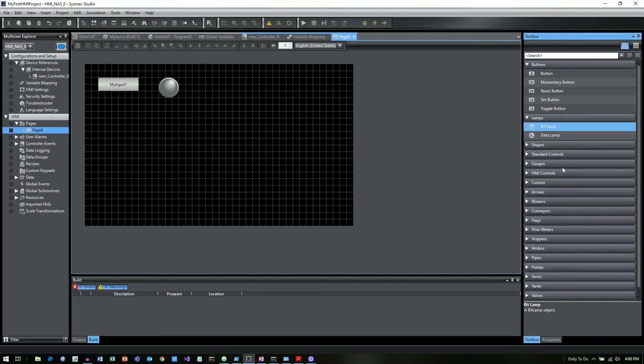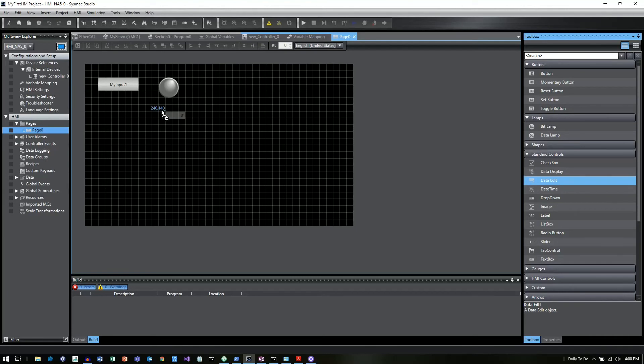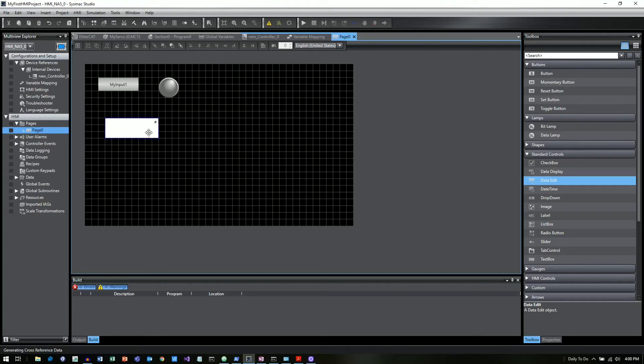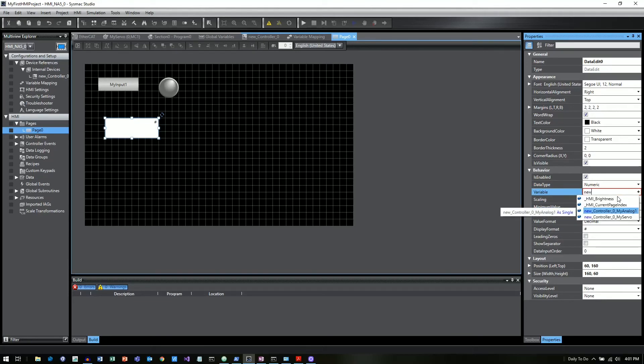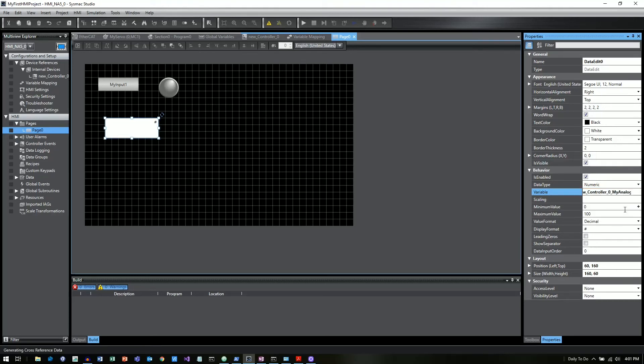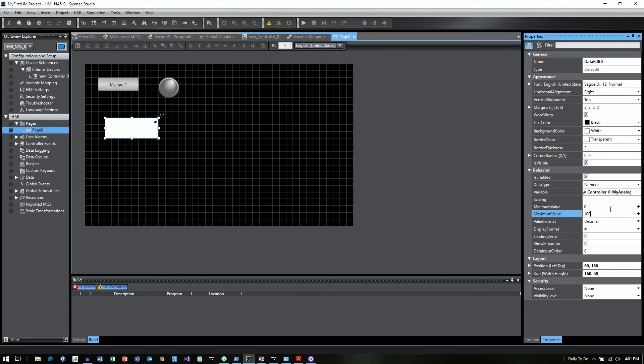And then the other thing we could do is we could put a data edit field, which is basically like an input, an analog input. So I'll just drag it over here. Now I'll go back to Properties. And there's all sorts of things you can set here. So we're going to go ahead and set the variable to new underscore controller. And we're going to go to MyAnalog1. Now, with the data type, we can set that as numeric or Boolean or text. So if you were just looking for a string value, you could set that as a string. Or if you want that to be numeric for entering analog values, you can set it that way. And you can see there's scaling. You can set minimum, maximum values. So right now it's set from 0 to 100.